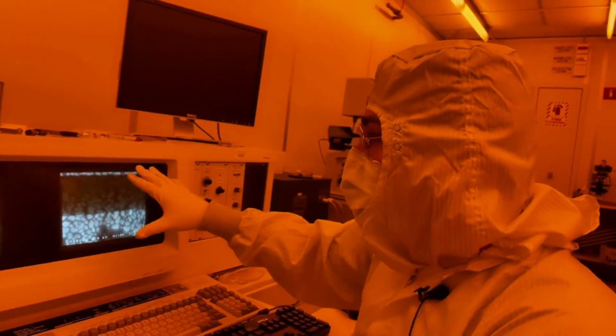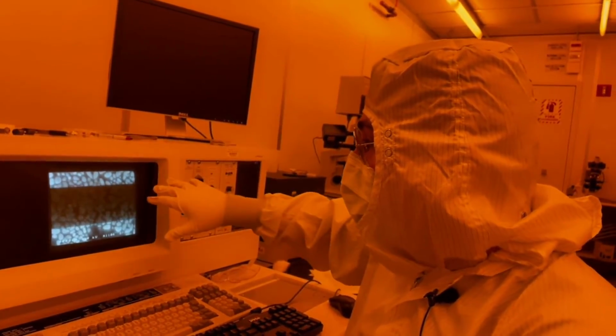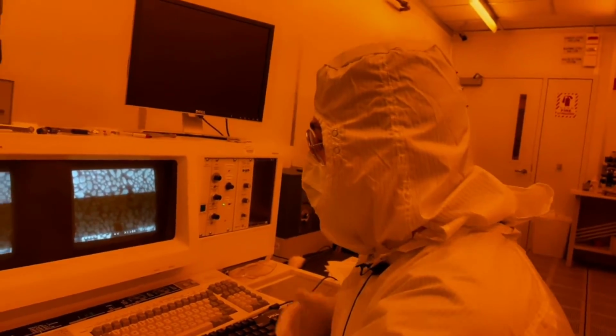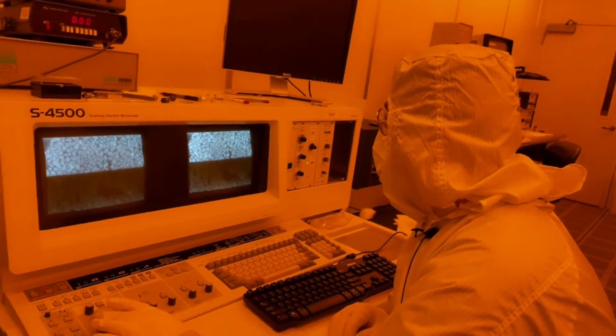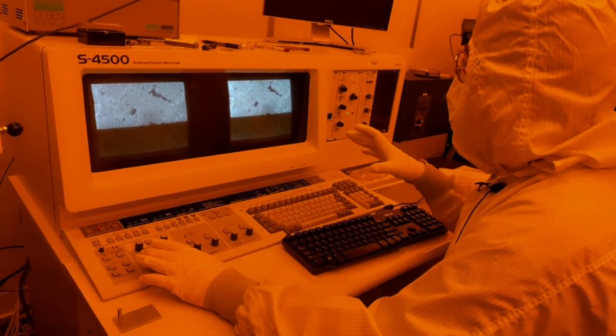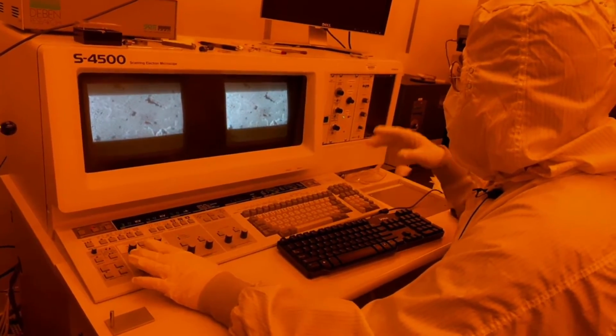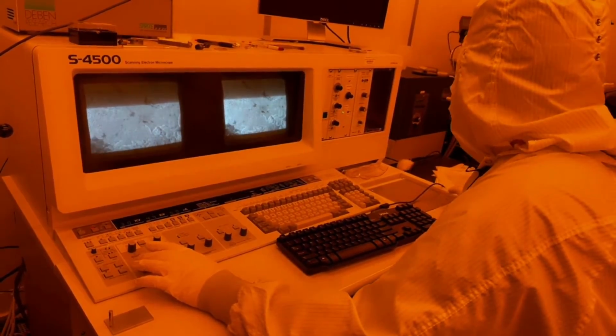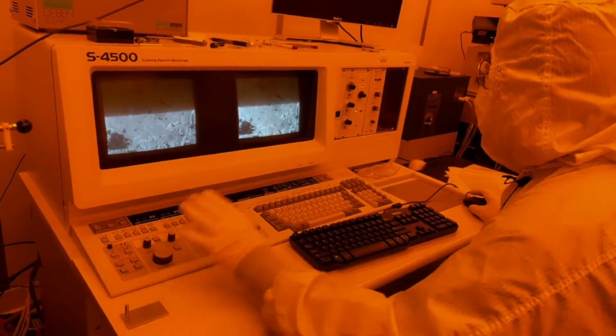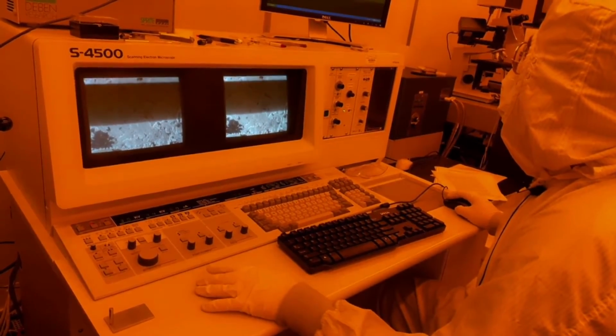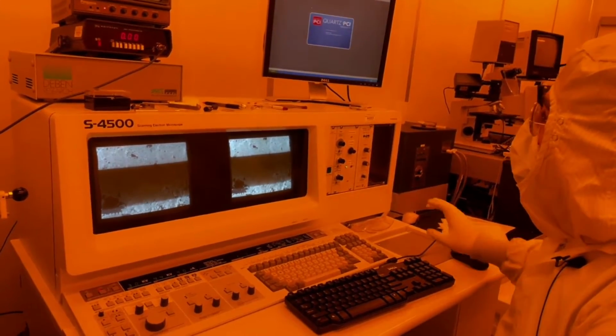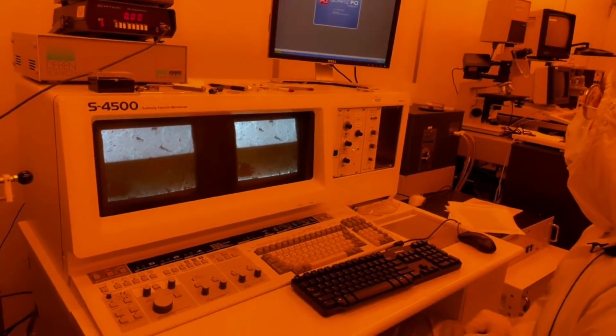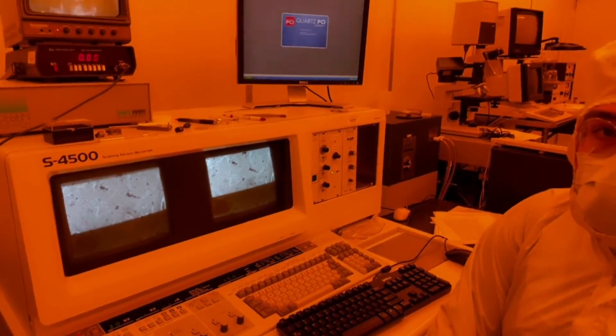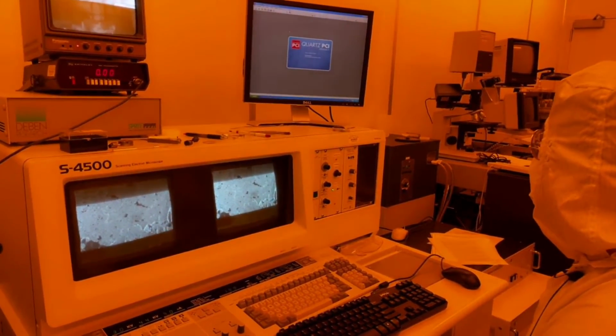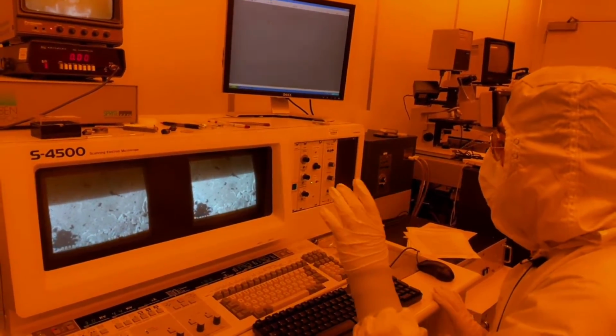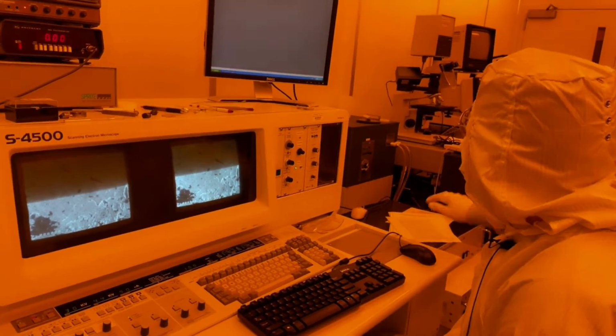It's less important for this sample because all you have here is nanospheres of gold. But just in general, when you're talking about nanostructures, you want to have a lower contrast once you get to your actual image. The next step here is to take this image that we have on here and transfer it onto a computer. For that, we have this Quartz PCI slow scan software. It's basically a USB connection between this scanner and this computer.